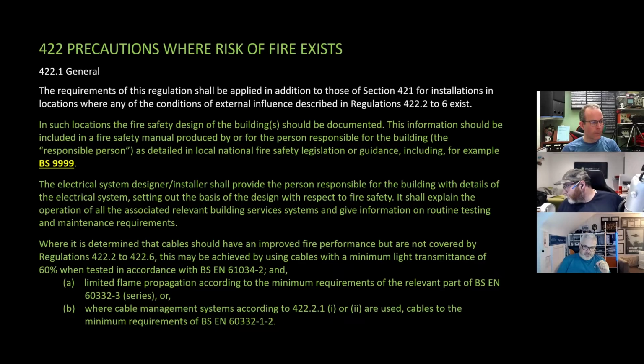This may be achieved by cables with a minimum light transmittance of 60% when tested in accordance with BS EN 61034-2, another standard to buy, and a limited flame propagation according to the minimum requirements of BS EN 60332-3, or where cable management systems are used, cables to the minimum requirements at 60332-1-2. And breathe.